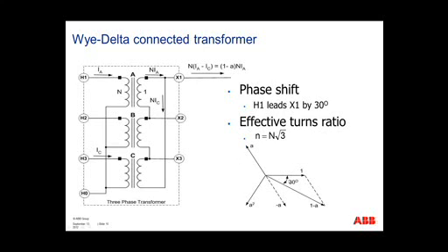When you do this, because of this new magnitude, you affect the turns ratio by a square root of 3. What this does for you is it actually saves the number of physical copper turns inside the transformer. This now gives you a new turns ratio multiplied by the square root of 3.